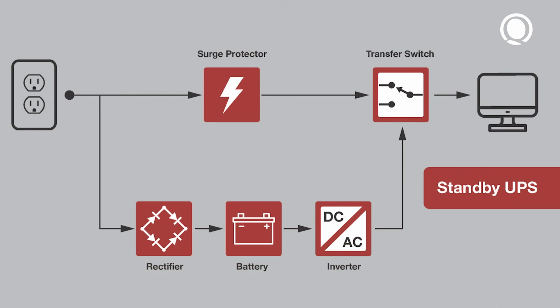There's three basic types of UPSs on the market today. There's a standby UPS. These are the ones you see at Walmart, Best Buy. They're relatively inexpensive. And the way they work is power comes into the UPS. Almost all of them nowadays have some power conditioning, which amounts to a surge protector. So if you get a big spike, it'll take the spike out of the signal coming in. Then the power goes to what's called a transfer switch inside the UPS.